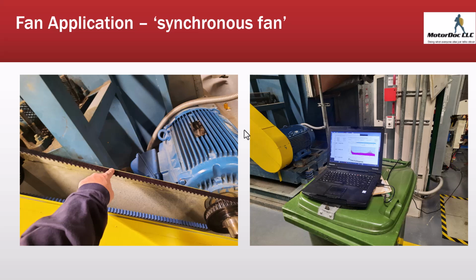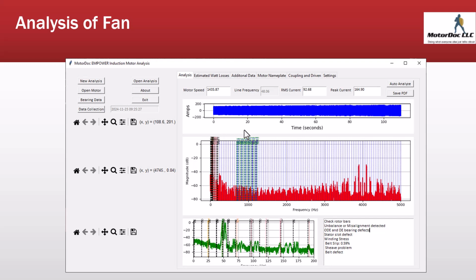So let's get into some of the energy-related stuff. This one is a fan application, a synchronous fan. We were investigating this because of damage to the belts. And when we took a look at it and started reading down through everything, of course the belt slip is not a lot. ESA and MCSA are not as affected by varying frequencies during operation. There's filtering that can be done, so this is all accurate. You can see there's actually 3 peaks as this thing's shifting back and forth through its frequency.